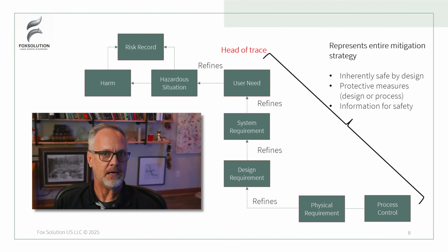Now, in many companies I've been involved in, and I would say maybe even more often than not, people don't look at the P1 and the P2 factor. They only look at P. That's because they can see in the field how many occurrences of the harms have happened. But this mechanism, how does the hazardous situation play into it, and what is the occurrence rate of the hazardous situation? They don't understand that very well, so they just don't track it.